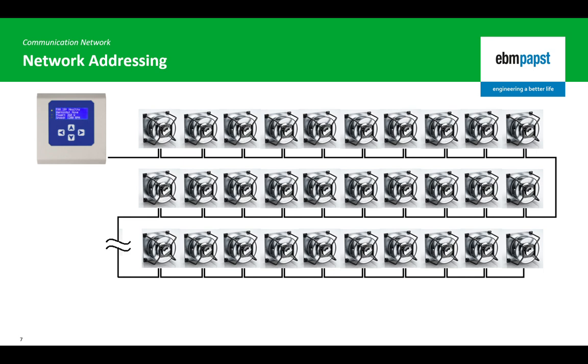When initializing a new communication network of EBM PAPST electronically commutated fans, the MDC identifies each fan individually by its serial number. It searches the network for the fan with the earliest serial number and assigns it to address 2. It then repeats this process, assigning each fan with an address in sequence until all fans in the network have been found.